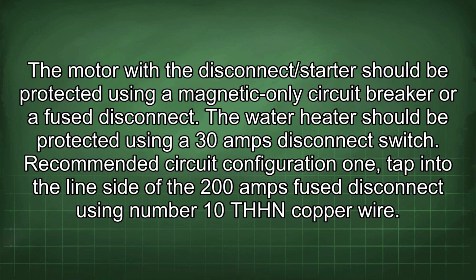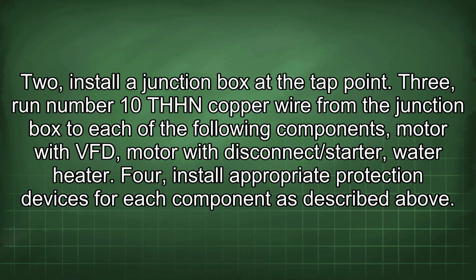Recommended circuit configuration: 1. Tap into the line side of the 200 amps fused disconnect using number 10 THHN copper wire. 2. Install a junction box at the tap point. 3. Run number 10 THHN copper wire from the junction box to each of the following components: motor with VFD, motor with disconnect/starter, water heater. 4. Install appropriate protection devices for each component as described above.